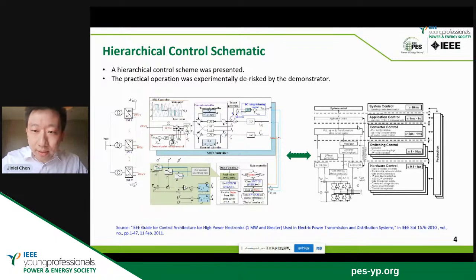In line with the IEEE standard, we developed a suitable hierarchical control structure for this type of converter. It includes several control layers. The application control layer is performed in the main controller, and it can operate under several control modes, such as droop control, power control, and DC voltage control. Also, the commands are calculated in the main controller as well. The commands and references are sent from the main controller to the submodule controllers. The submodule controllers perform the current control and PWM modulation. So this is the basic control structure of this converter.